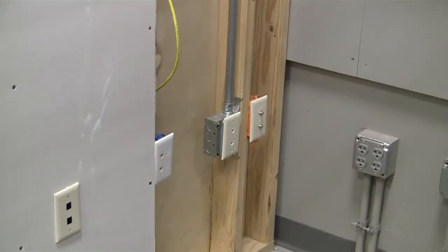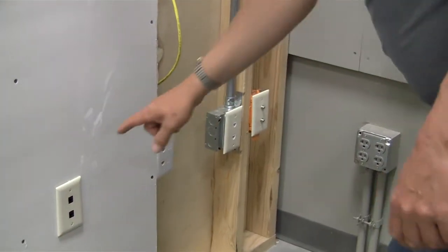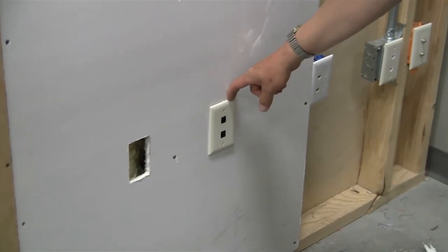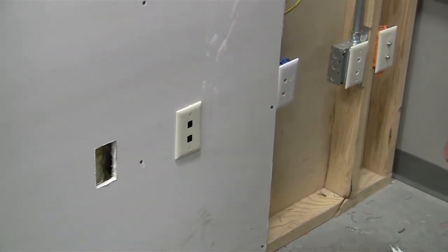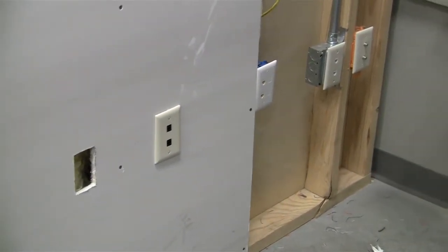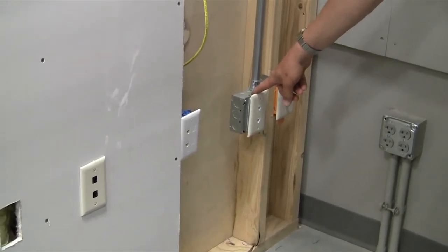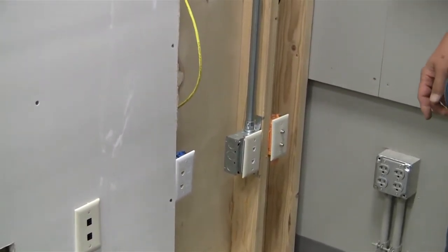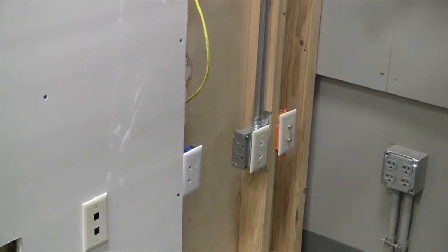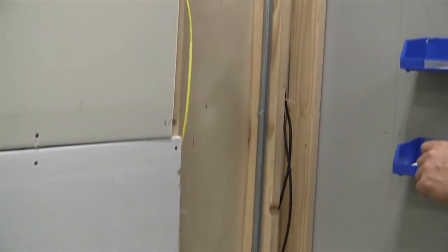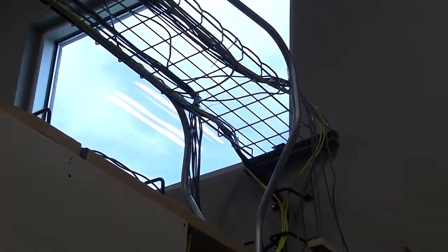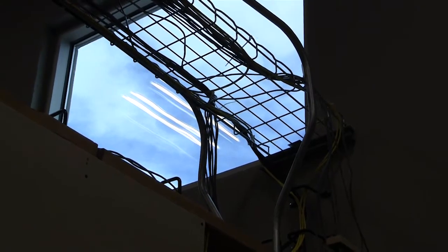Okay, so this is the work area side. Notice 2 wall jacks put into a wall plate, into the sheetrock, and 2 into the conduit. Now those 2 are terminated to those 4 I showed you on the patch panel. And if you look, everything's been pulled in. And if you go up to the top, notice that all the cables are neatly put up onto the rack and dressed in. And that's what I'm looking for.